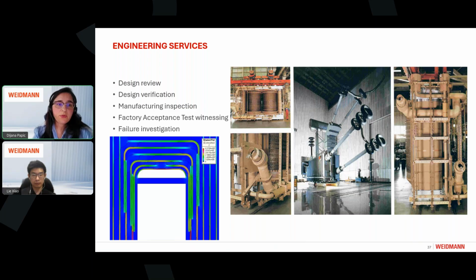Due to the huge impact of the tolerances, manufacturing inspection is also crucial, and at the end, of course, FAT witnessing of the transformer is also part of our engineering service. And if needed, in case of a failure or a damage case, we are also happy to jump in for a failure investigation and a root cause analysis.